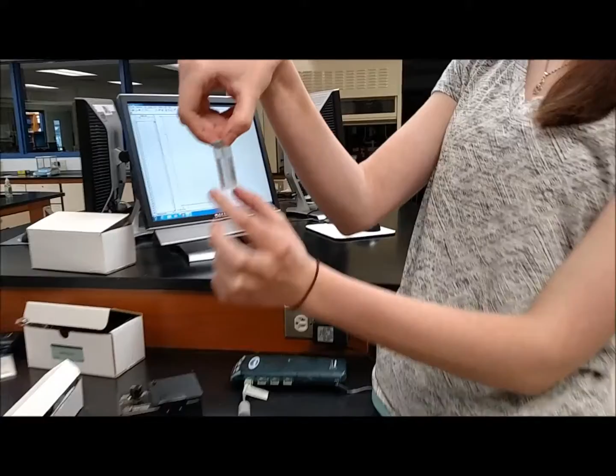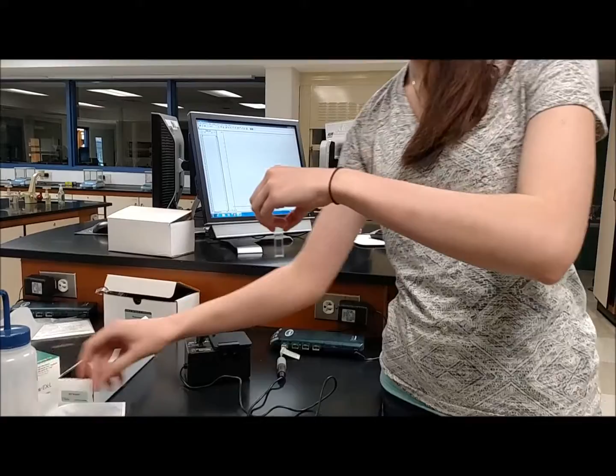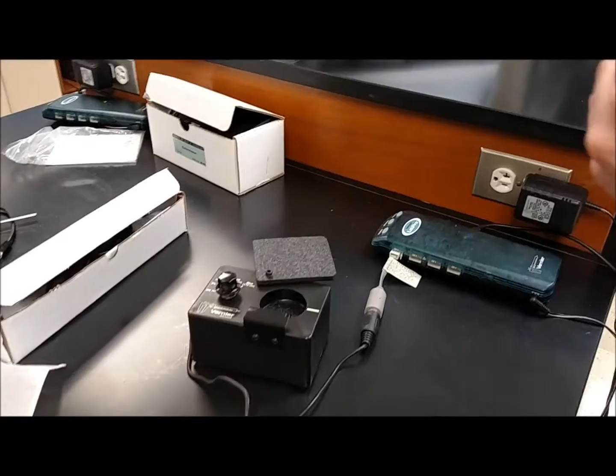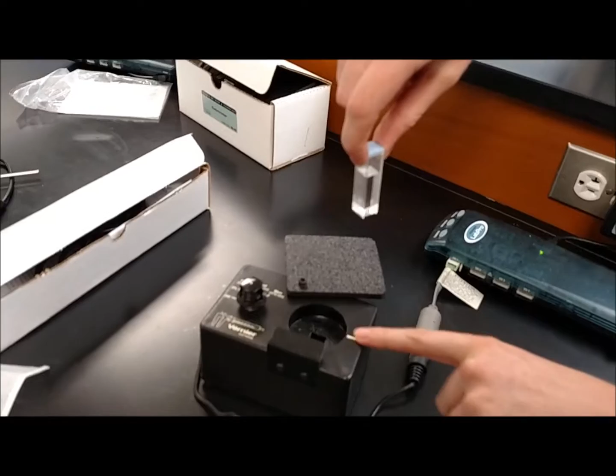Alright, and then with the cuvettes, you need to make sure that you handle them using only the top of the ridged sides. There are 2 sides that are ridged and then 2 sides that are smooth. So you make sure that you're holding it by the ridged side so that your data isn't compromised by finger smudges. So once you do that, you take a little cuvette tissue to wipe off the sides to again make sure that there's no smudges and so on. Then you open up your colorimeter and put the cuvette in with the clear side, or the smooth side, facing the line, because that is where the reading will occur.